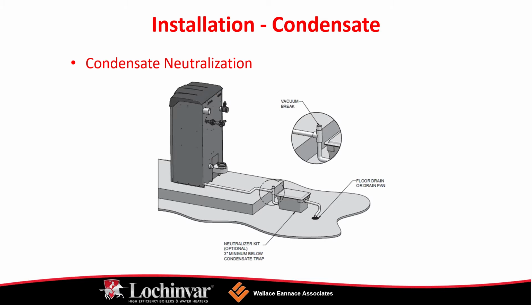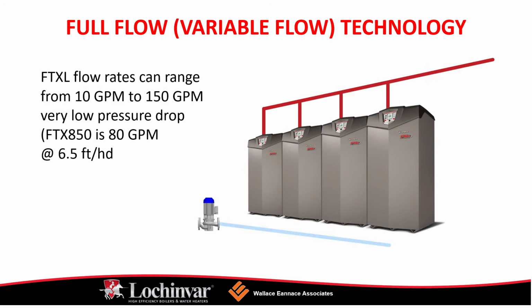And neutralizing condensate is very important, because we condensate quite a bit, just about a gallon per hour for every 100,000 BTUs when at full condensing mode. So larger units use larger neutralization kits in that manner. You don't want to connect the condensate lines with copper or it will rot out pretty quick. So we advise using PVC.